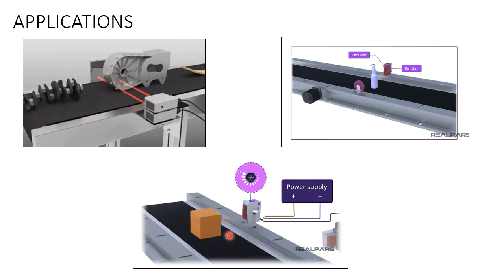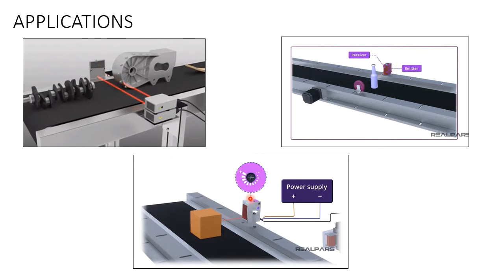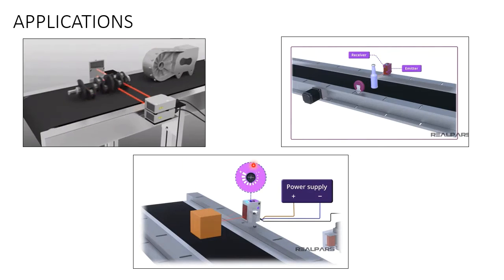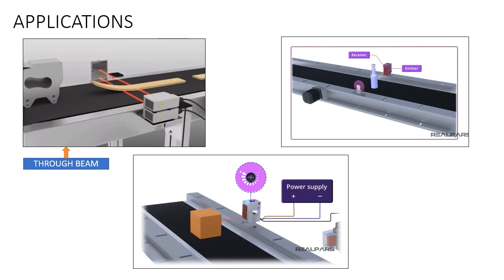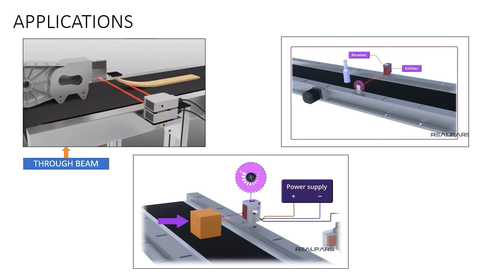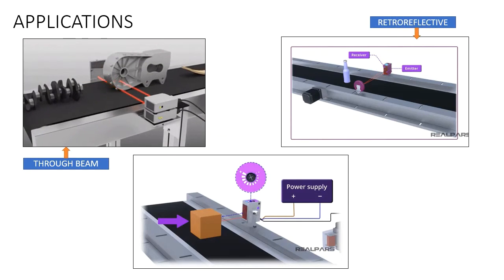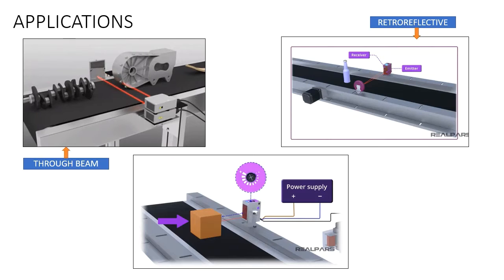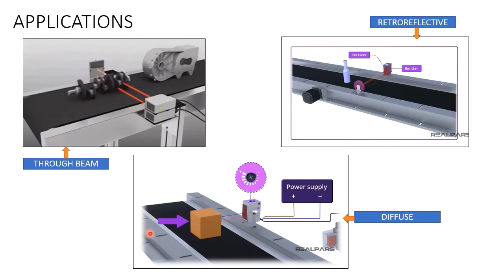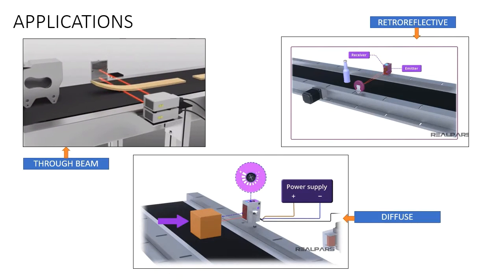In the third application, there is only one sensor and the object placed in front of it gets detected. Now, can you guess which sensor type is used in each case? The first is a through beam sensor — a separate transmitter and receiver with the beam obstructed. The second is retro reflective — emitter and receiver in the same housing with a separate retro reflector. The third is diffuse type — a single sensor with built-in transmitter and receiver, no reflector needed.